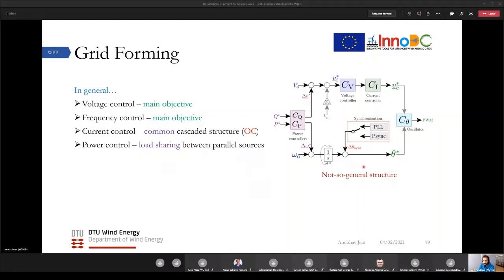the frequency reference. And that's what I think the Scottish Power Renewables people must have implemented, because they implemented a virtual synchronous machine control in their grid forming onshore wind power plant test. I don't have any details from them, but what they say is that it's the virtual synchronous machine method, because it's the most researched, and it's quite simple to understand coming from a power system perspective.